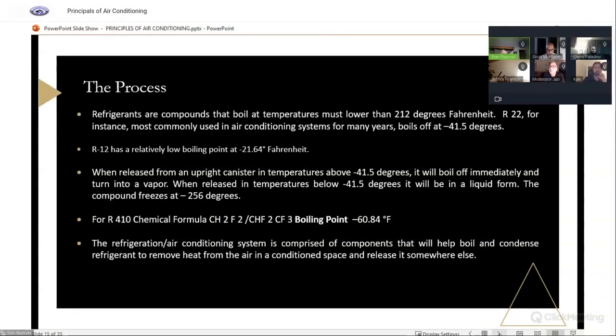And they do have a freezing temperature as well, but we're not going to ever see that. And then for R4, what's that? Can I ask a question? Yes. The R22 versus the 410. So what I've been telling people is on older systems that use that R22, if your outside condenser needs to be replaced, the air handler in the attic or in the basement is also going to have to be replaced most likely, because it will not marry the two, right?